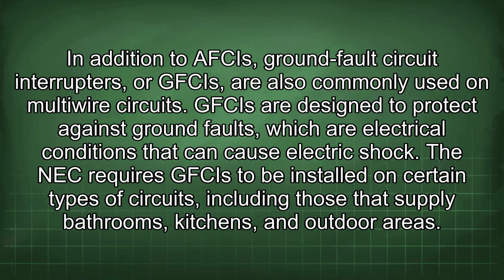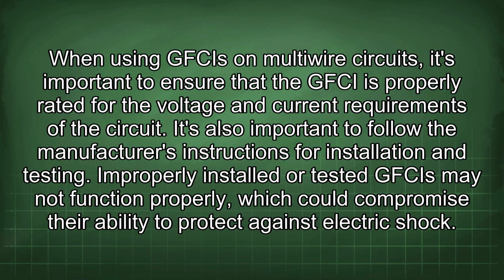In addition to AFCIs, ground fault circuit interrupters, or GFCIs, are also commonly used on multi-wire circuits. GFCIs are designed to protect against ground faults, which are electrical conditions that can cause electric shock. The NEC requires GFCIs to be installed on certain types of circuits, including those that supply bathrooms, kitchens, and outdoor areas. When using GFCIs on multi-wire circuits, it's important to ensure that the GFCI is properly rated for the voltage and current requirements of the circuit. It's also important to follow the manufacturer's instructions for installation and testing. Improperly installed or tested GFCIs may not function properly, which could compromise their ability to protect against electric shock.